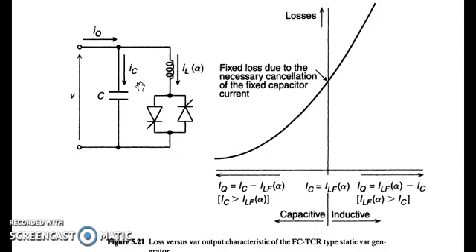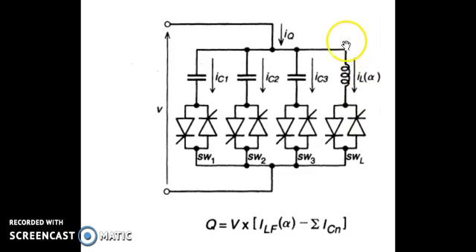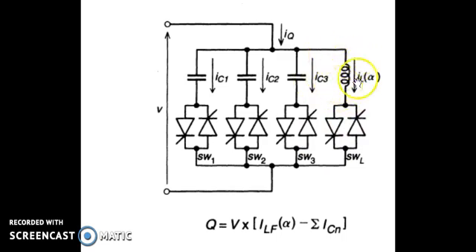When there is a deficiency of reactive power, we can switch the inductive component completely off and rely on the capacitive component already in the circuit to supply the required reactive power. Another possible scenario uses a large inductor controlled by bidirectional thyristor devices, coupled with a set of capacitor components which can either be thyristor-switched or fixed. The thyristor controlled reactor has extra controlling ability — its firing angle is set based on the reactive power requirement of the system and is completely controllable.